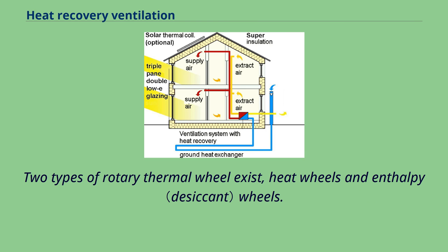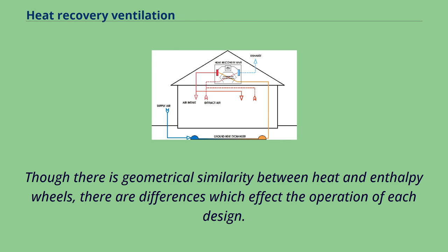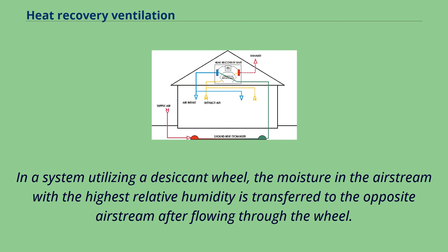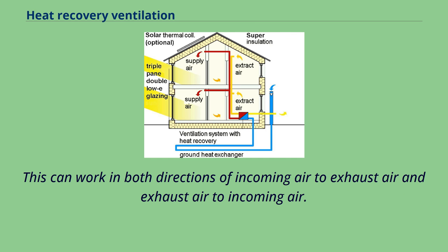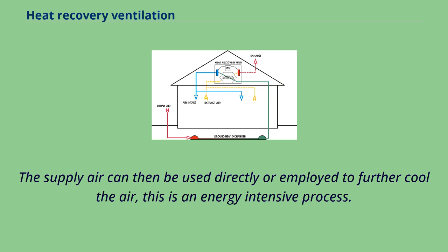Two types of rotary thermal wheel exist: heat wheels and enthalpy wheels. Though there is geometrical similarity between heat and enthalpy wheels, there are differences which affect the operation of each design. In a system utilizing a desiccant wheel, the moisture in the air stream with the highest relative humidity is transferred to the opposite air stream after flowing through the wheel. This can work in both directions — incoming air to exhaust air and exhaust air to incoming air. The supply air can then be used directly or employed to further cool the air, though this is an energy intensive process.